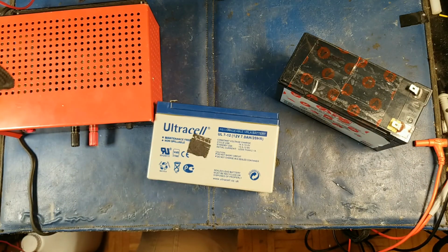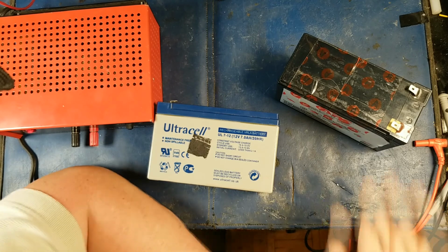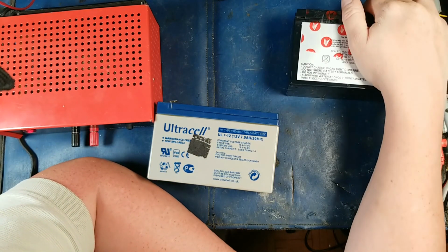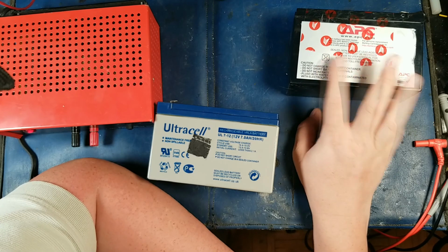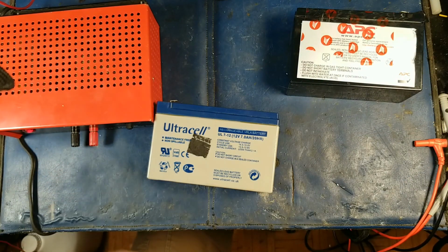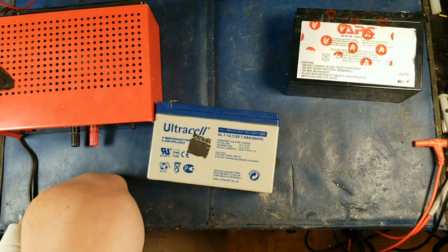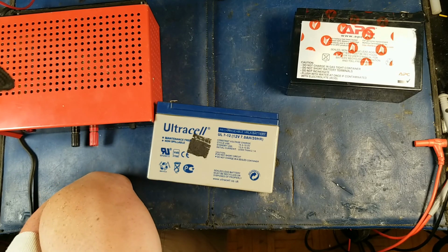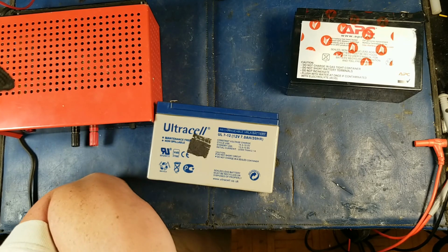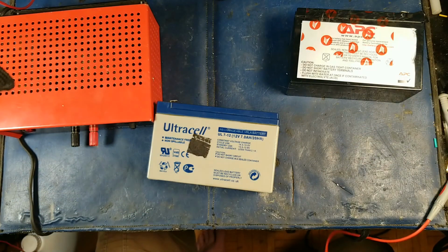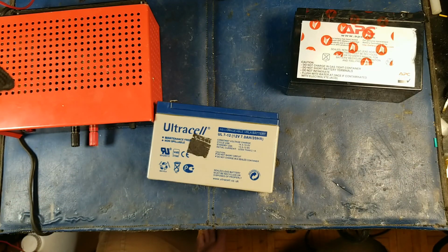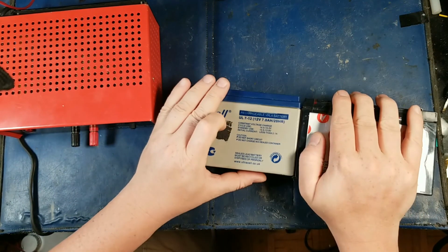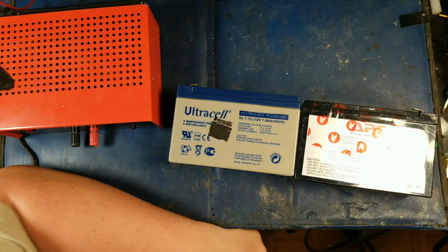A little tip for you: APC UPSs typically run at higher than 13.5 volts on standby — they'll actually run at 14.2, which is stupid. You can do that with flooded lead-acid batteries, but AGMs dry out. You can actually change the voltage set point on those UPSs if you hack into the firmware. On older ones, you can plug into the serial port and do it, and hook up a 1500 watt halogen light to recalibrate the units, but that's another video for another day — I don't really want to do that because you really only have to with APCs.